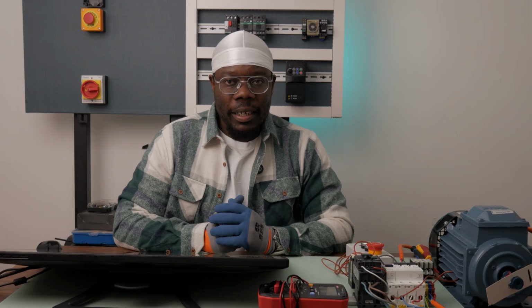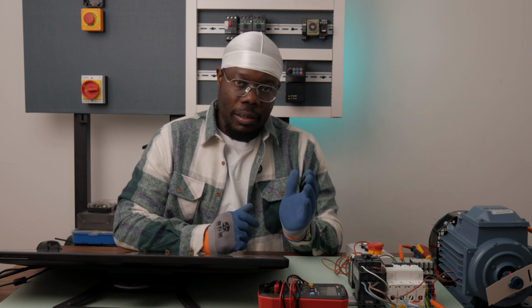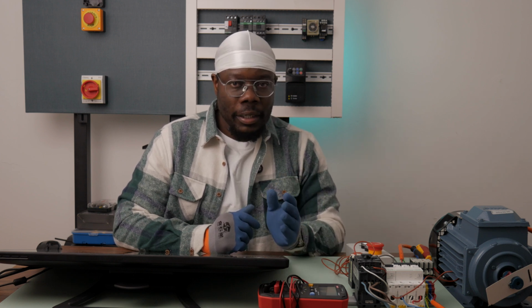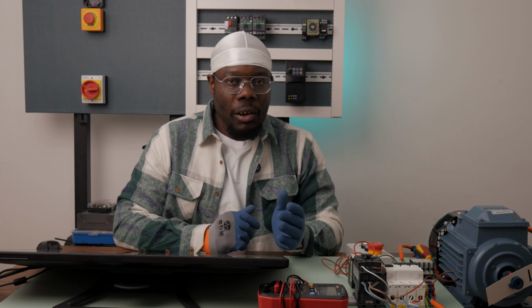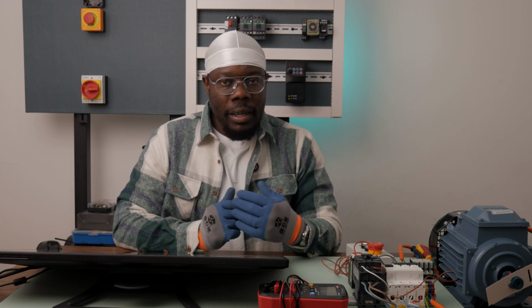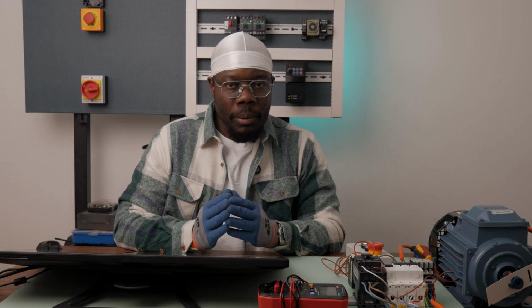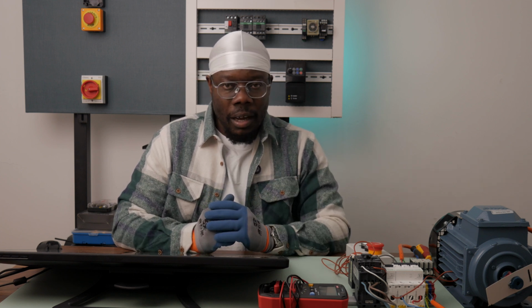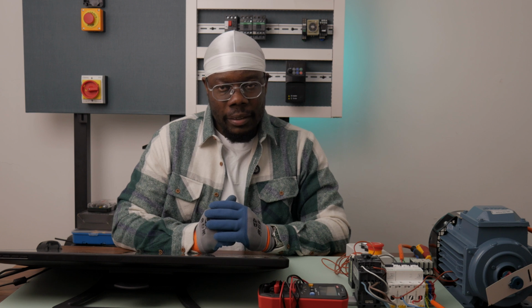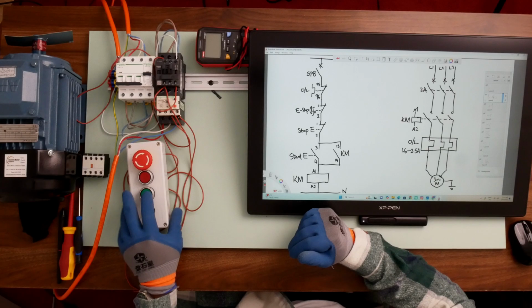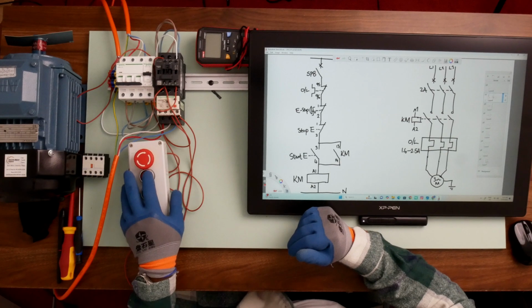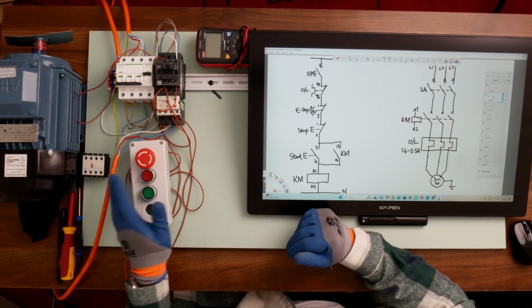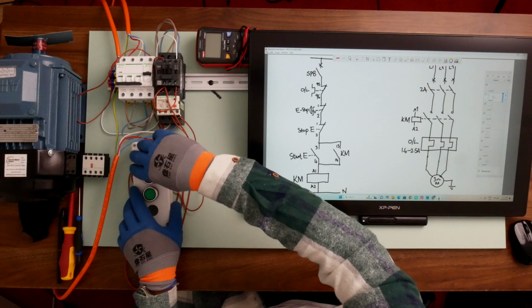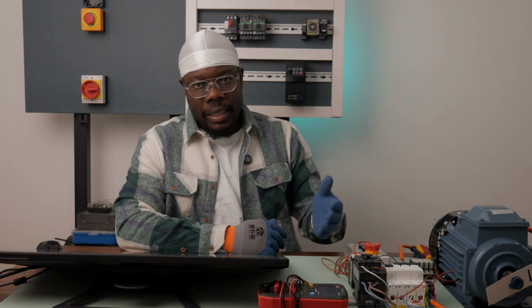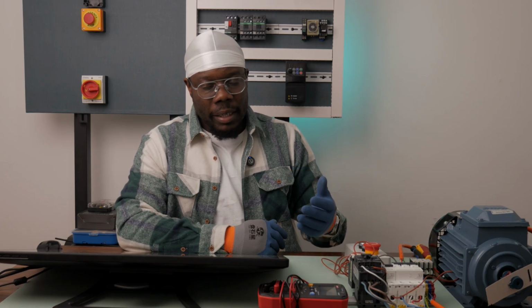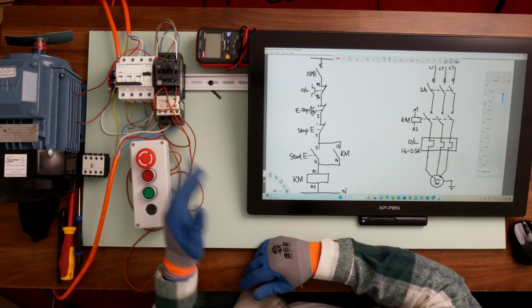Now is the time of reckoning. It's time to test if our control circuit and our power circuit works. So we're going to start by testing our control circuit, and then when we are satisfied that it's working properly, we'll proceed to switch on our power supply and test the power circuit as well. So yep, see, it's working. I can stop it, start, and then I can press my e-stop, and then when I release my e-stop, my circuit doesn't engage automatically. I have to press the start in order to start the circuit again.